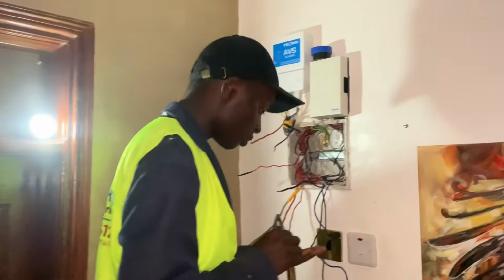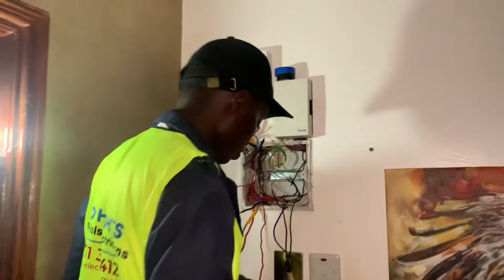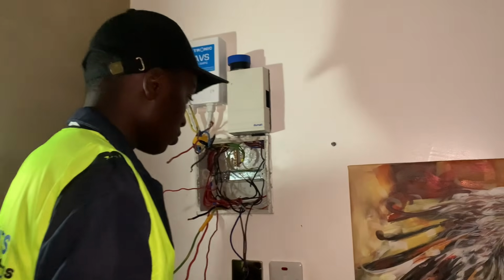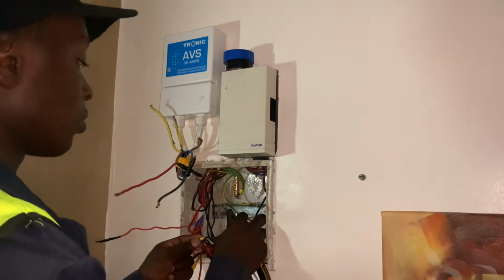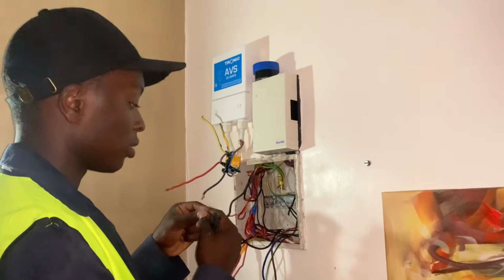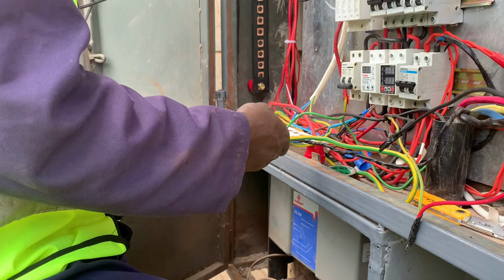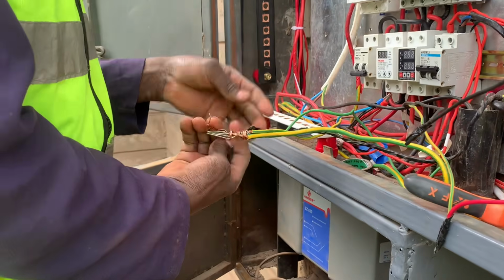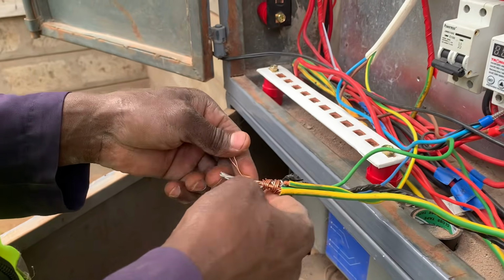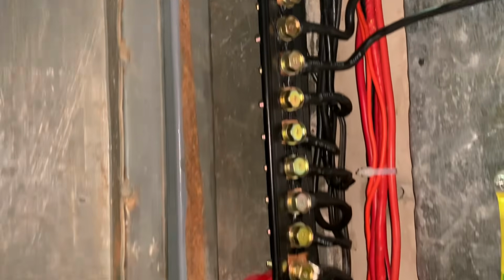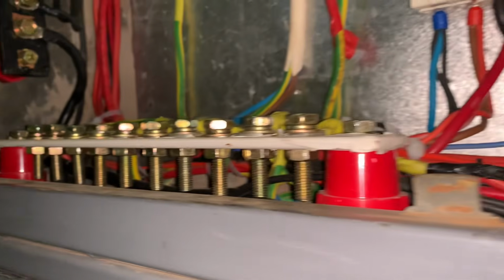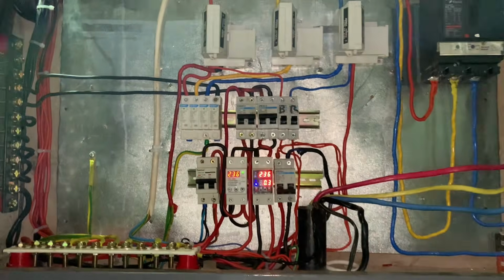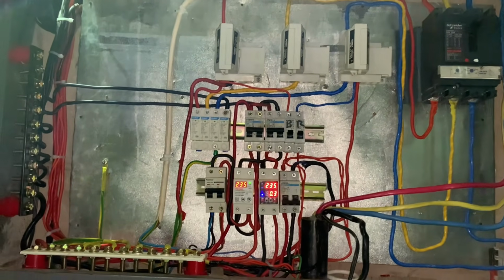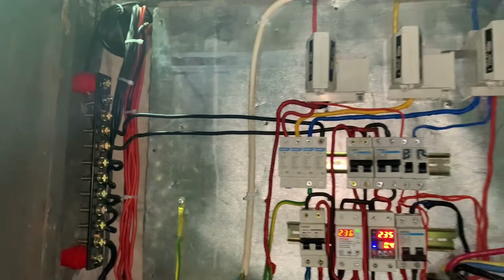In a three-phase distribution system, especially to a customer, there is no point of having single-phase consumer units. What if the customer decides to have a three-phase machine, whether it's upstairs or some part of the home? The three-phase connectivity should be consistent in any electrical connection, especially with the main board or the distribution boards. Another important aspect is to note that the neutral is only one connection, serving these three phases. Therefore, the neutral must be taken with a lot of weight.